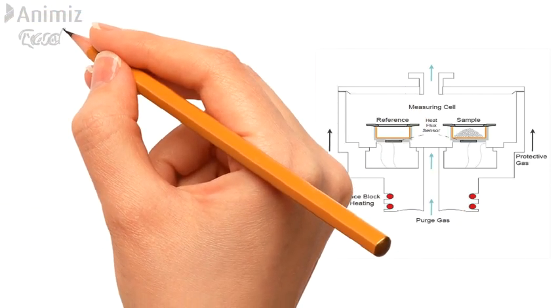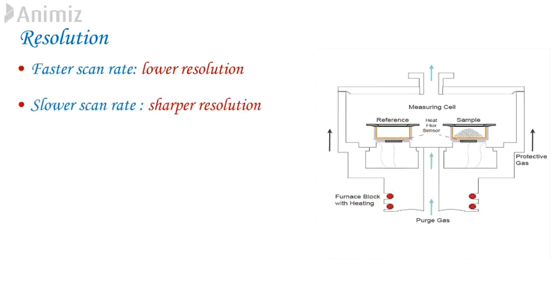3. Resolution. Because of thermal gradients across a sample, the faster the scan rate, the lower the resolution, and the slower the scan rate, the sharper the resolution. Thermal gradients can be reduced by reducing sample size and improving thermal contact with the pan by good encapsulation.